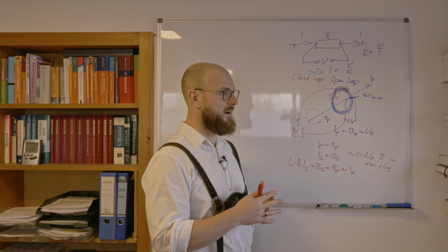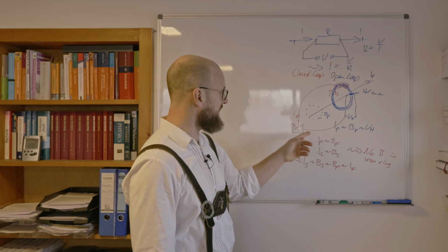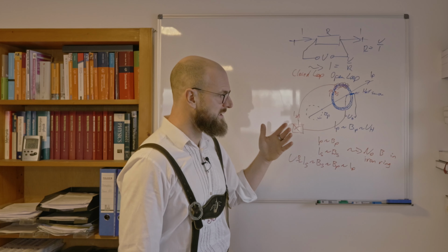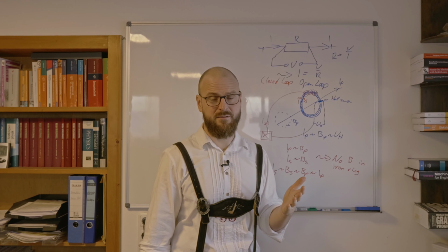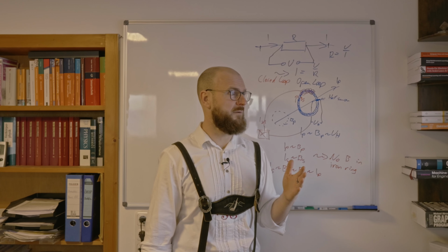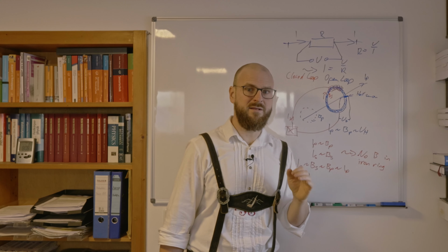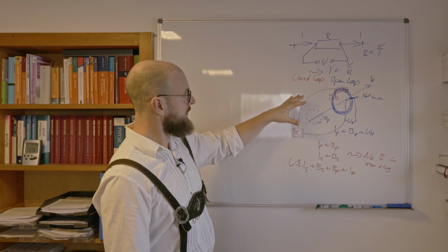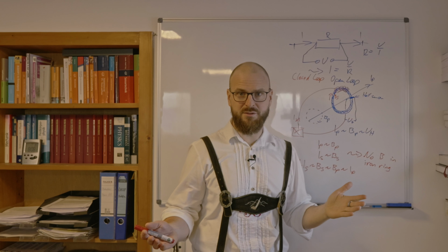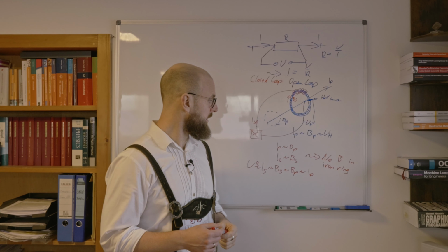There's no additional controlling or calculation involved in that system. So that control unit is quite simple, and for that reason it's quite fast. And that explains the fact that closed loop systems even have somewhat better dynamic behavior. And so those closed loop systems are the most often used system for measuring currents indirectly.